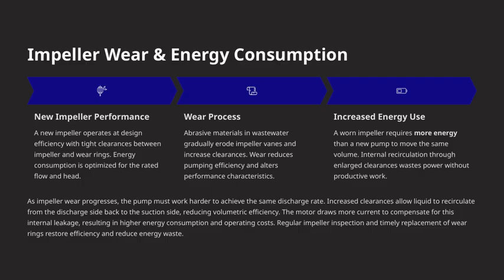That's why regular inspection and timely replacement of wear rings are so important. Restoring the impeller's original clearances helps maintain efficiency and reduces unnecessary energy waste. Staying proactive with maintenance keeps the pump running smoothly and economically.